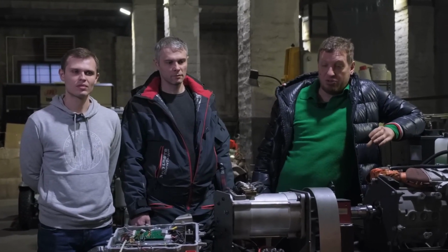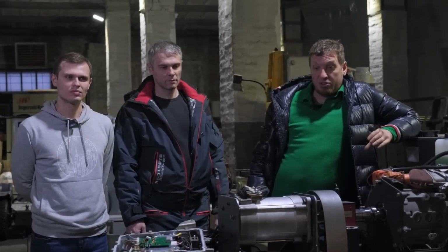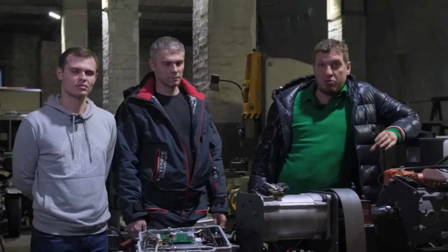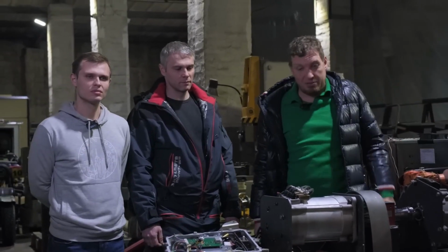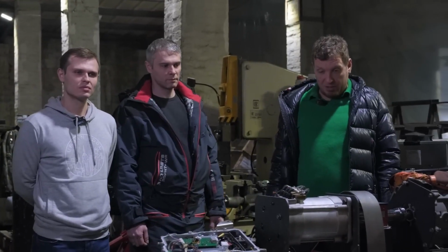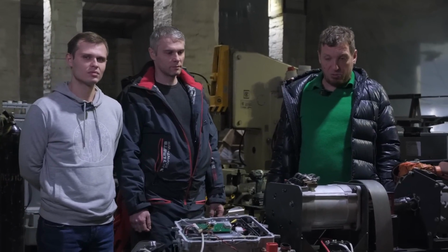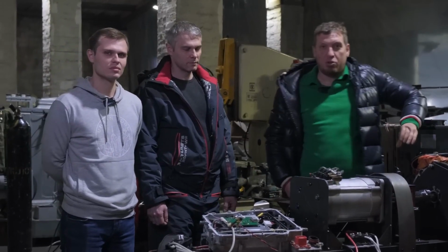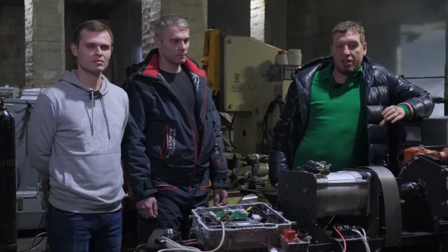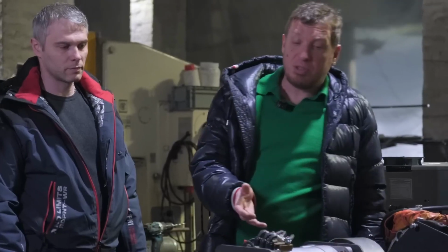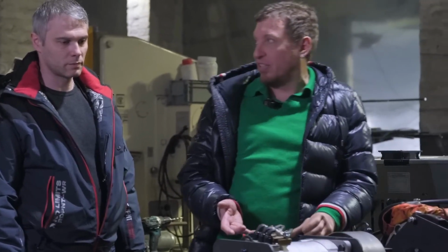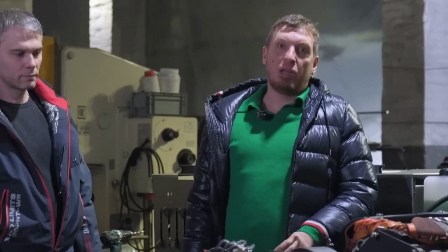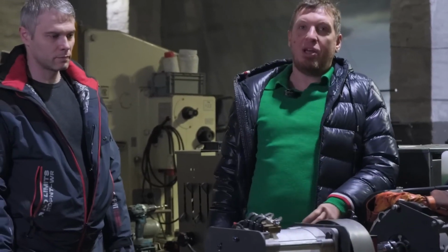That's fine for vehicles. The topic of synchronous motors is interesting. We'll try something, I think, rewind one ourselves, set it up and test it. But honestly, we really didn't see anything remarkable or groundbreaking from Mr. Duyunov. It's just an ordinary motor. No better or worse than any other. With that kind of cooling system, it really won't last. It's just completely nonsensical, because it has neither fins nor a fan. What the manufacturers meant by the rated value, only they know. Maybe if it was floating in liquid nitrogen.